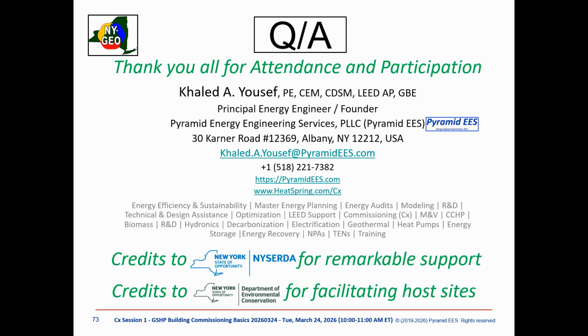If you have chill beams or low temperature heat emitters, the commissioning agent will really have to sit down with the project team and the design engineer to schedule multiple commissioning activities to sign off that the project is running well. Then you have to let the BMS system track your well fields to make sure you're not swaying up or down. Measure the BTUs, how much is being extracted from the earth and how much is being put back. That doesn't happen in a couple of days, it needs a year to look at it. Unfortunately my answer is long, but that's the reality of it.